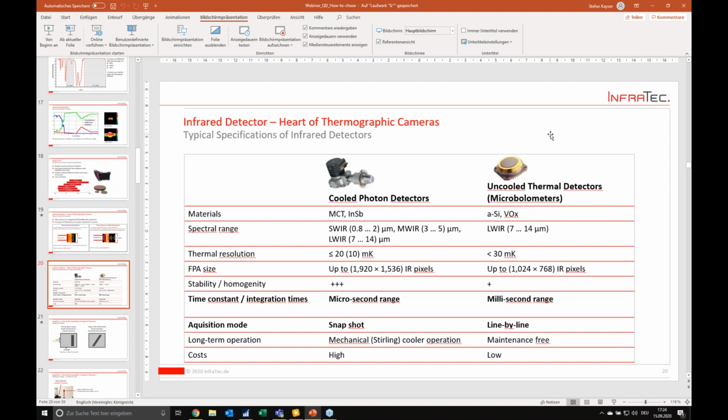But for measurement situations in industry or in R&D, we're talking about wide ranges of temperatures, not sharp and limited ranges, and then the top end of the current performance for both is again ±1% or ±1 Kelvin.